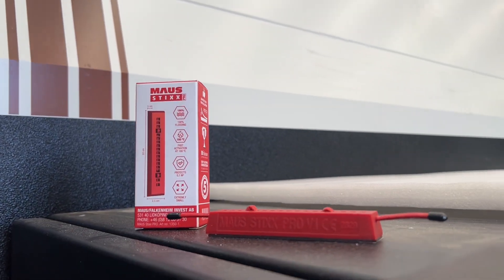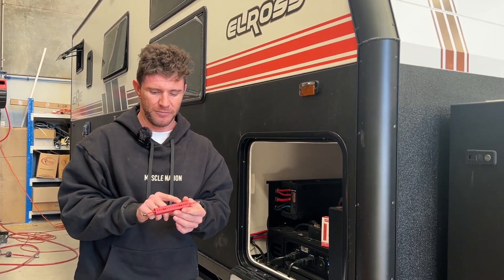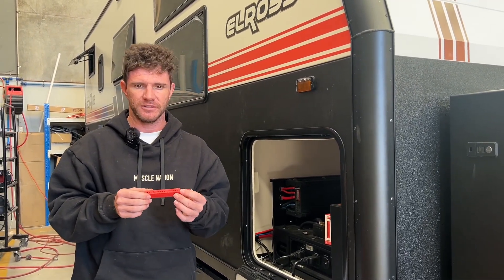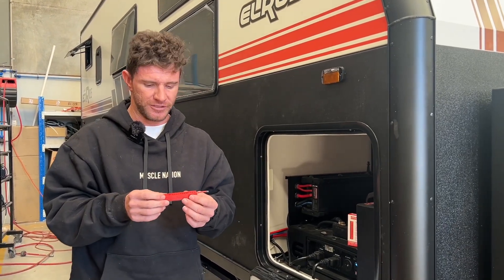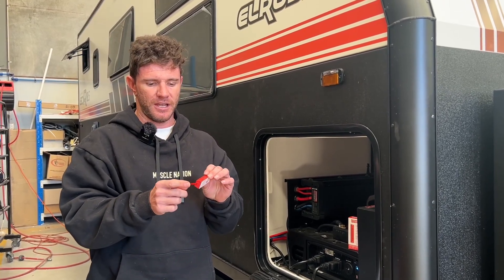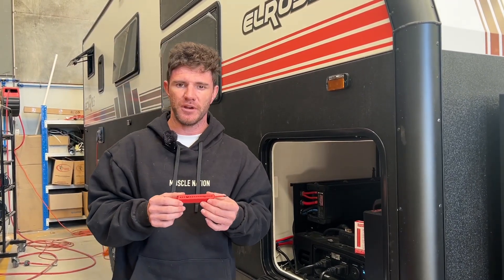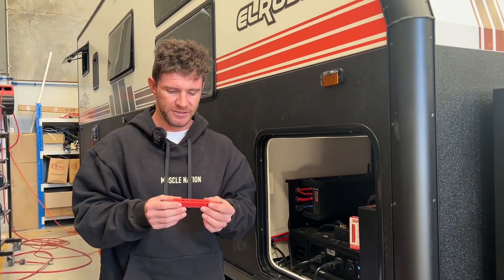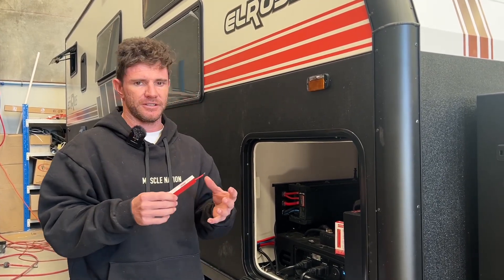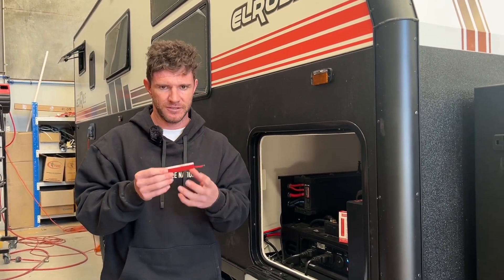The Maus Stixx Pro is made in Sweden and its innovative technology is basically a chemical compound potassium stick. Now potassium reacts with radicals like hydrogen and oxygen. So essentially what this chemical compound will do is, once this heat detection cable detects a temperature within this range of around 170 degrees Celsius, it will start a chemical reaction and the potassium will deploy, reacting with the radicals of the oxygen and hydrogen built up by the start of the fire.